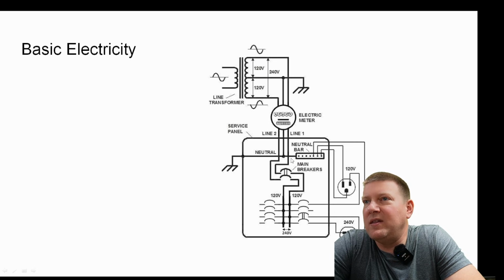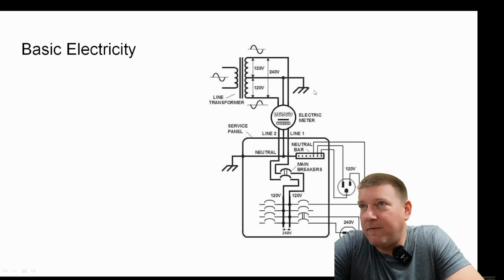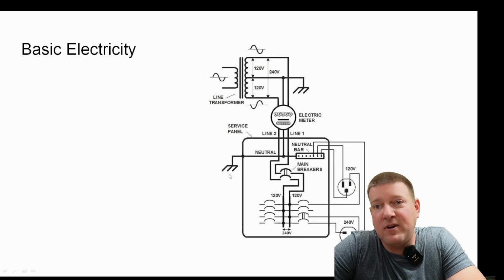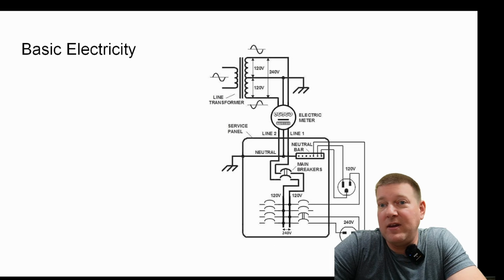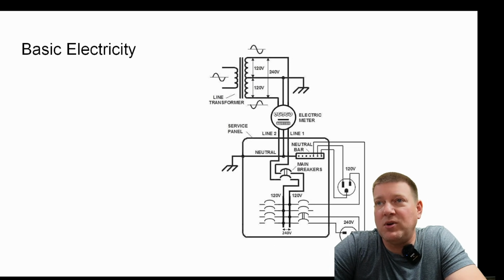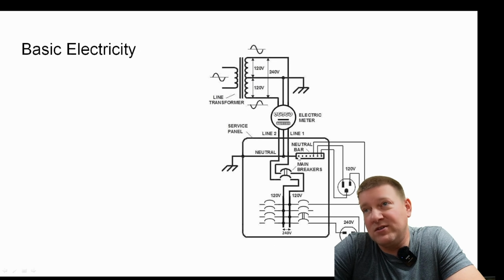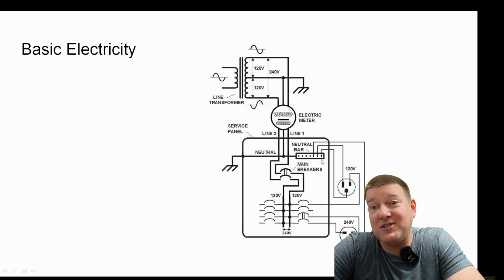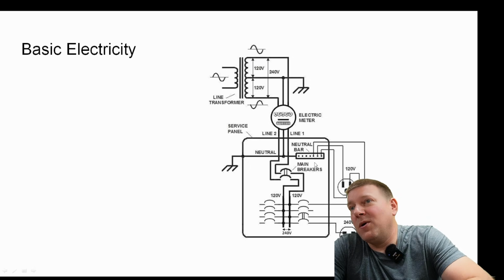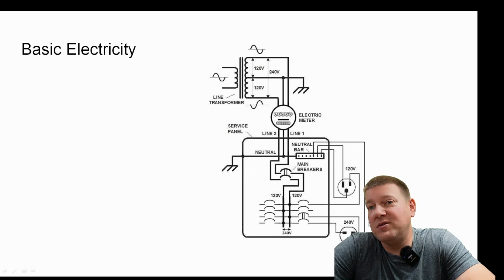So you can see that here's our ground coming in from the pole. So your house is tapped off at the same potential as ground on the pole. You can see here, this would be the stake on the outside of your house, or you would have, even in a commercial property like a hospital, a very large ground point or multiple. And here's the neutral bar. Notice it's attached, okay? So neutral and ground are always going to be at the same potential.